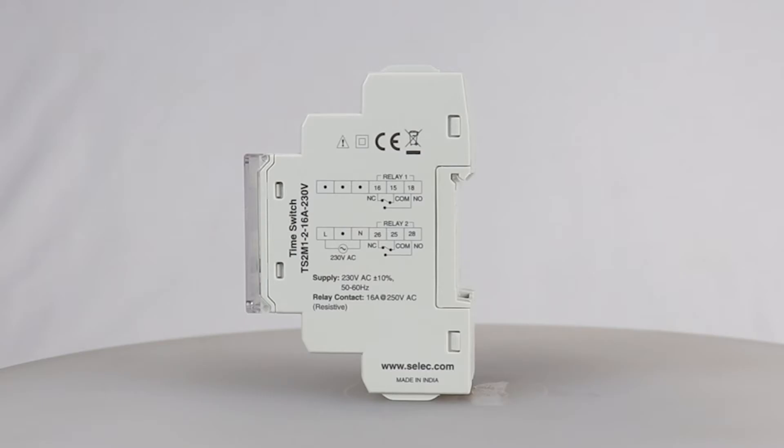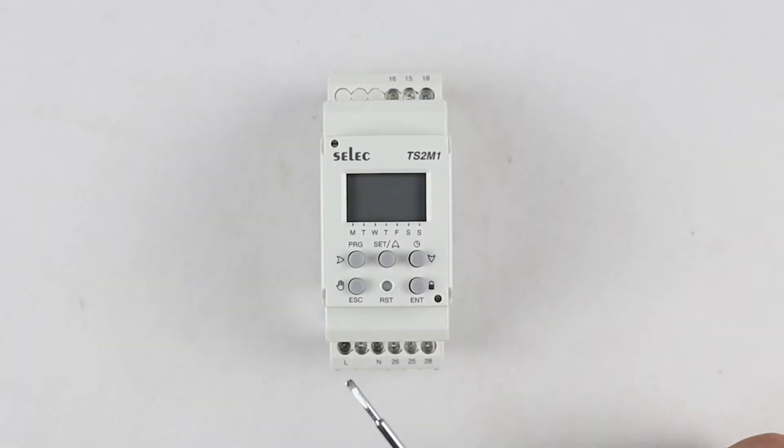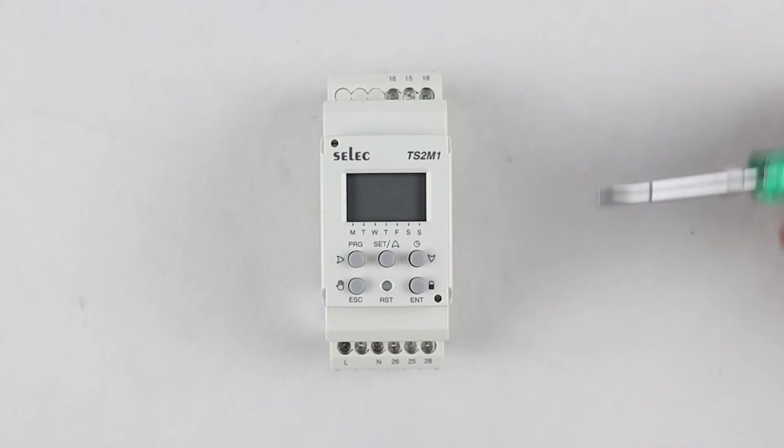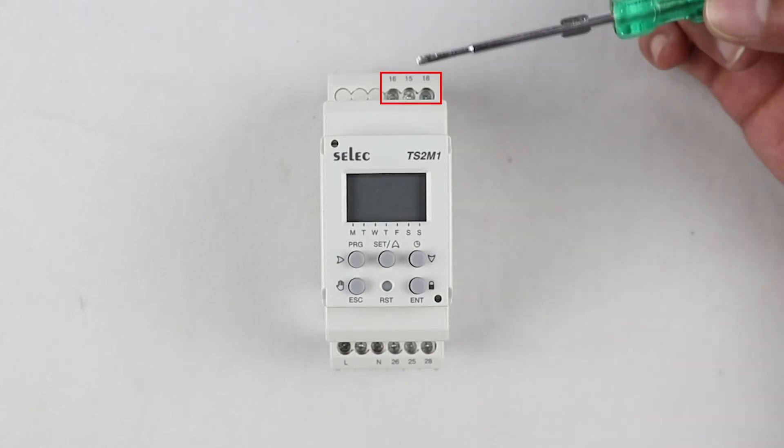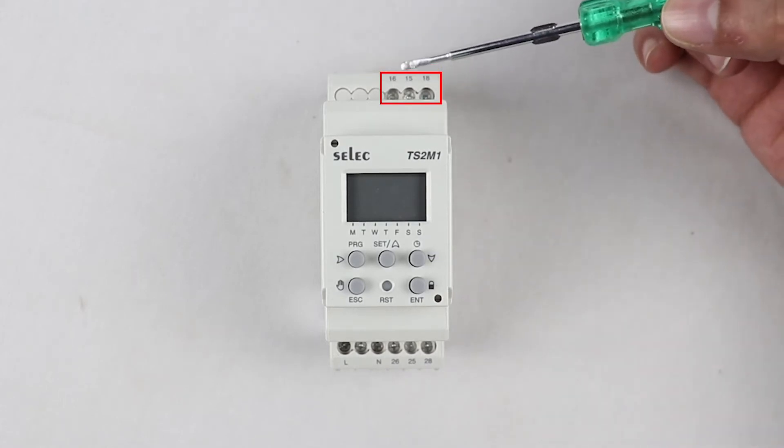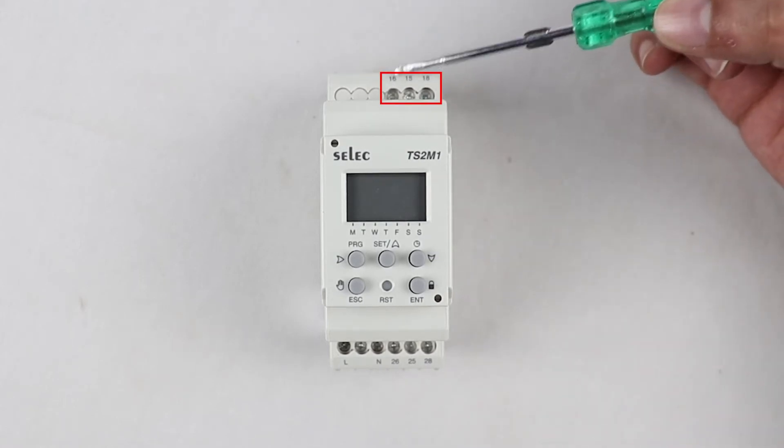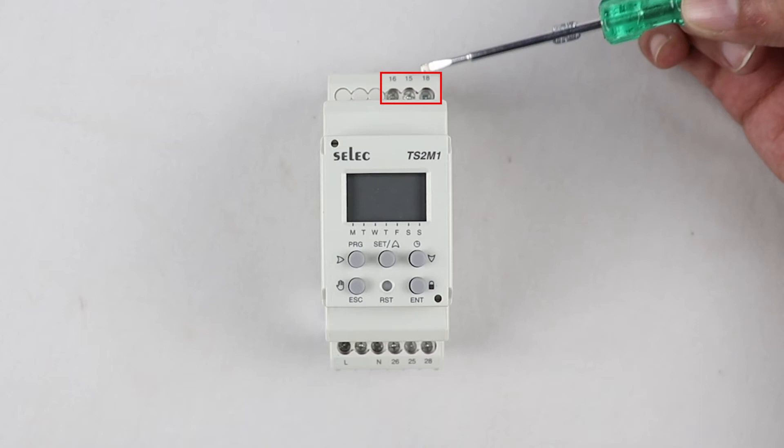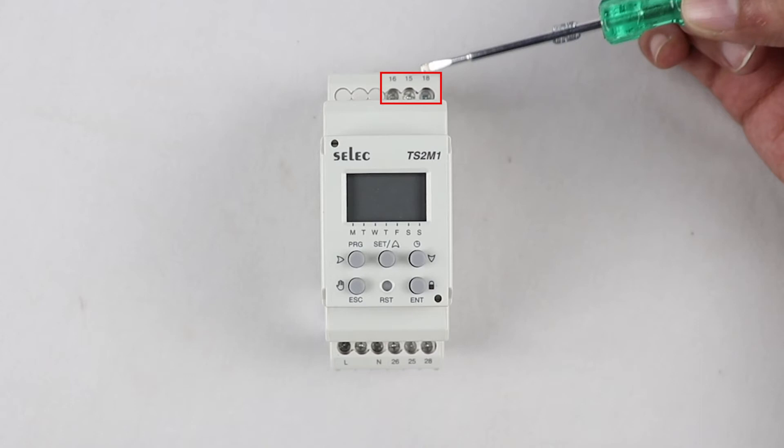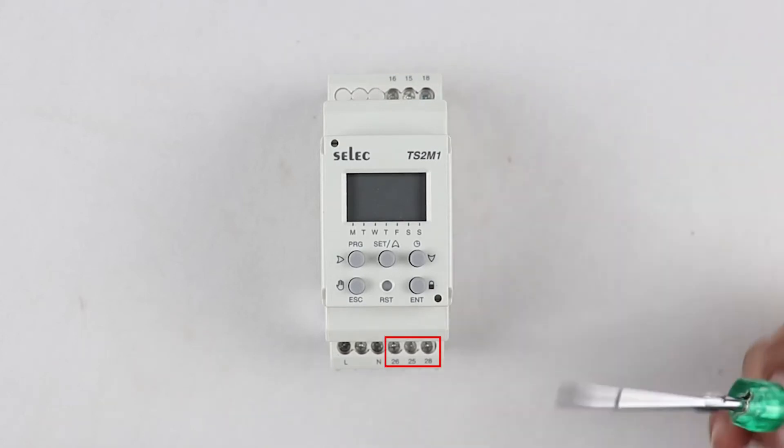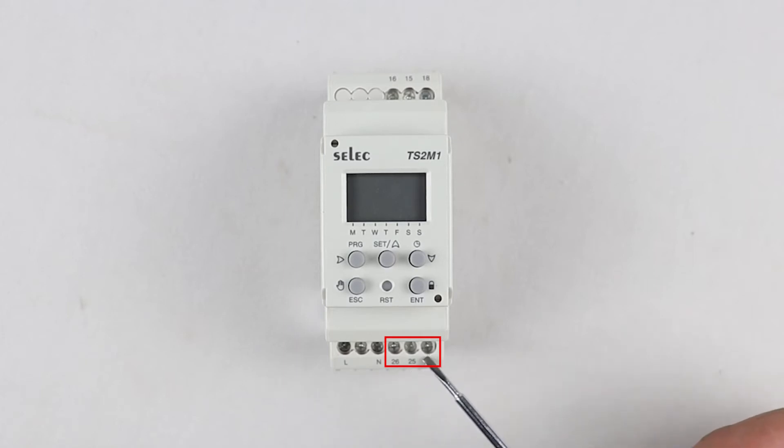Terminal connections are given on the right hand side of the product. To start with we will be connecting line or phase wire to L terminal and neutral wire to N terminal. Now the output for the first application is to be taken from N O of relay 1 which is terminal number 18. And the output for the second application is to be taken from N O of relay 2 which is terminal number 28.